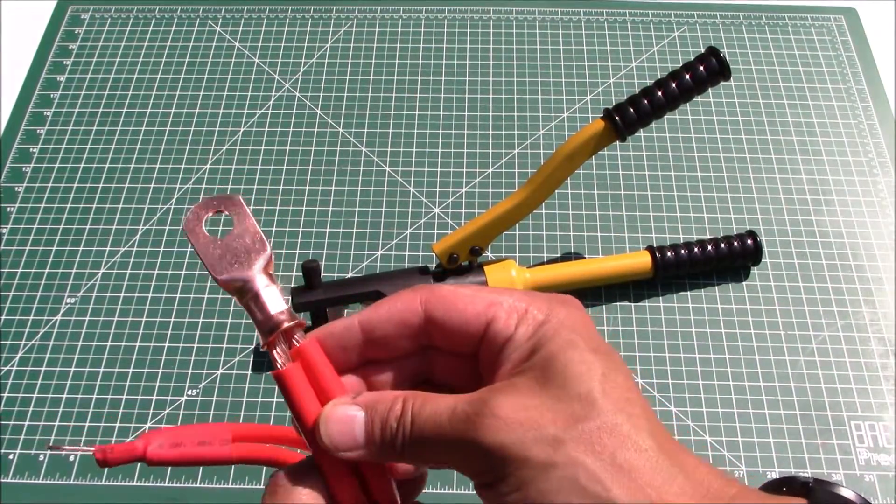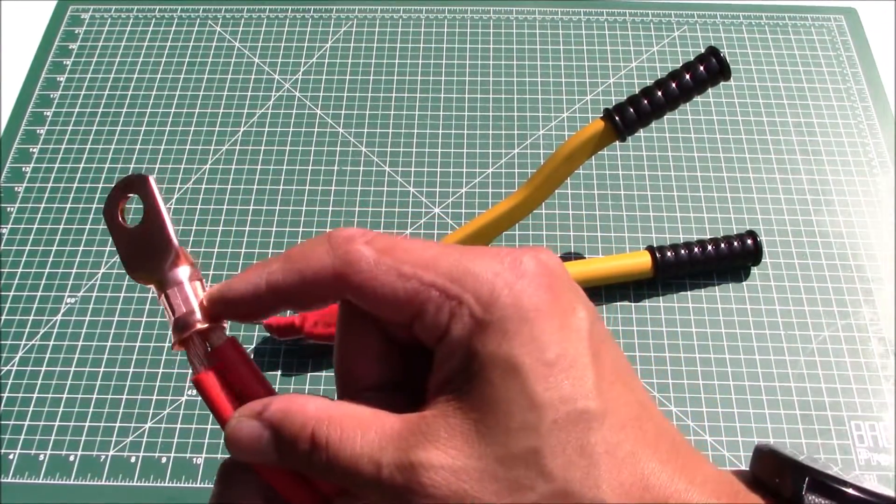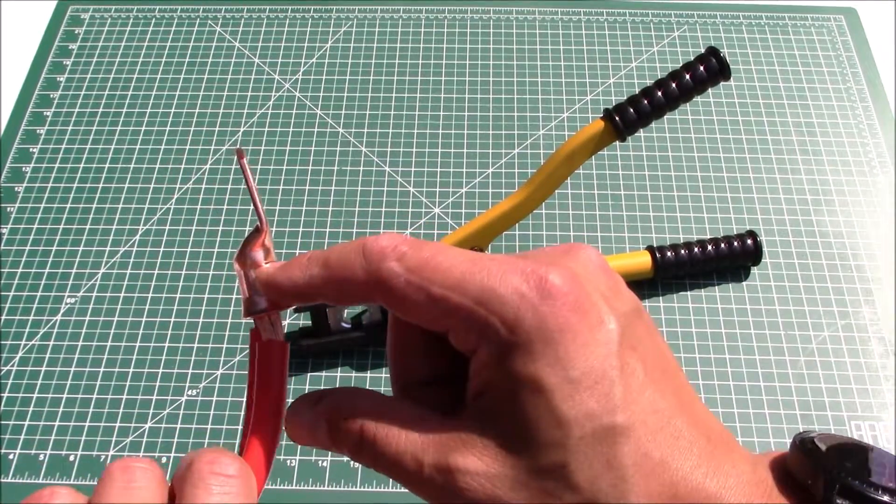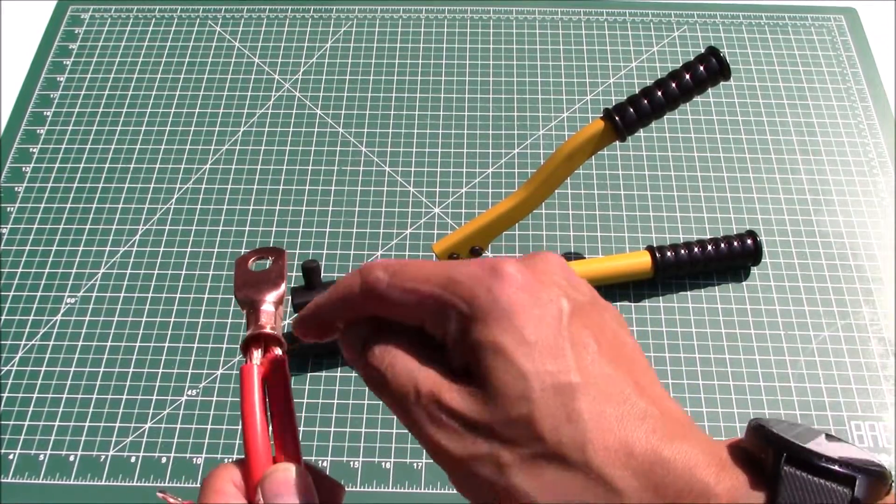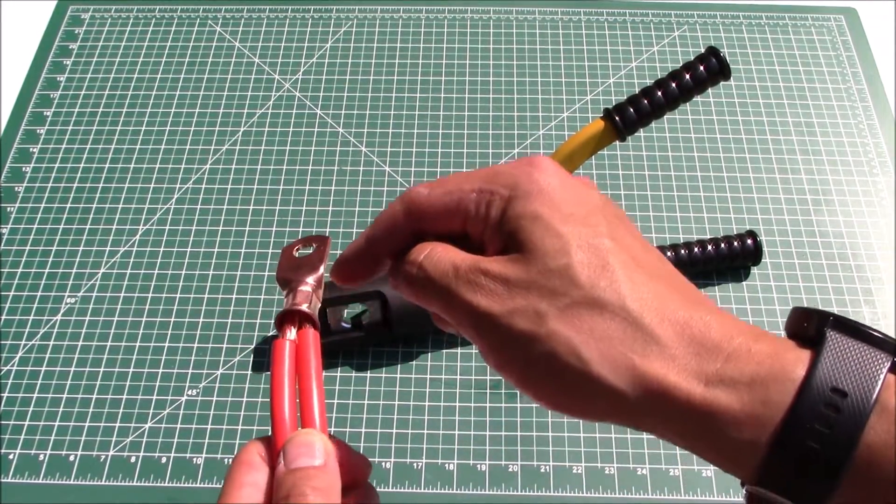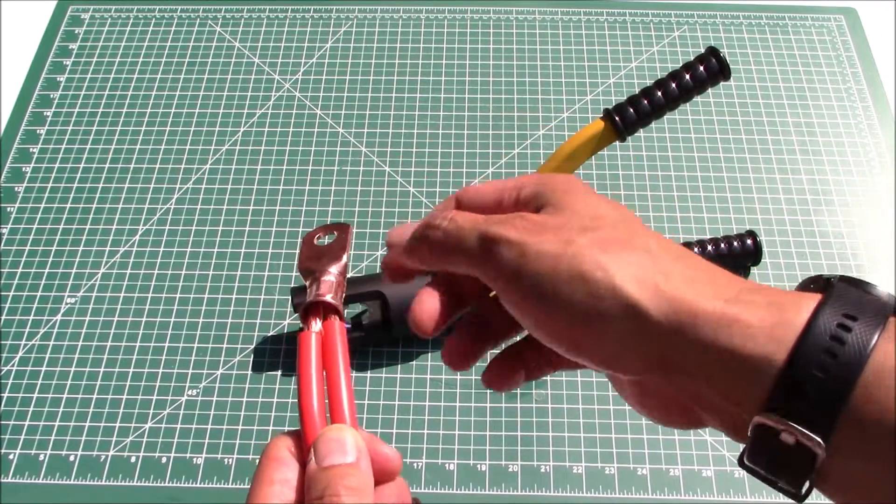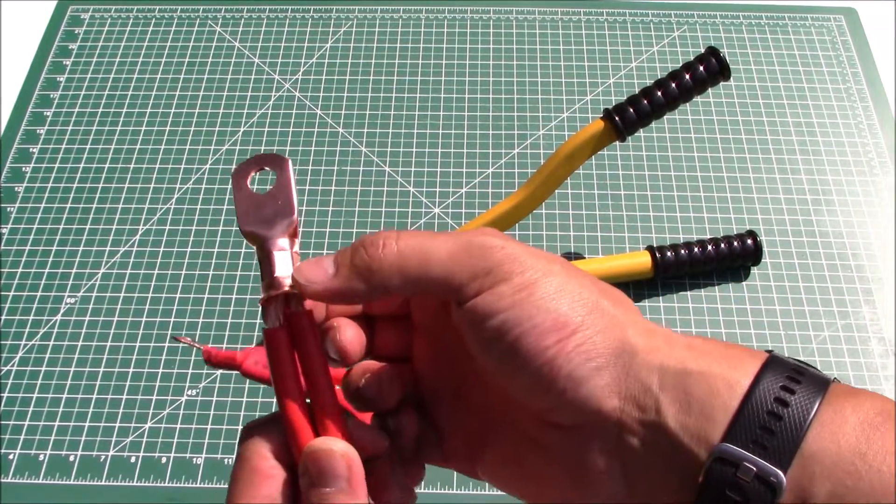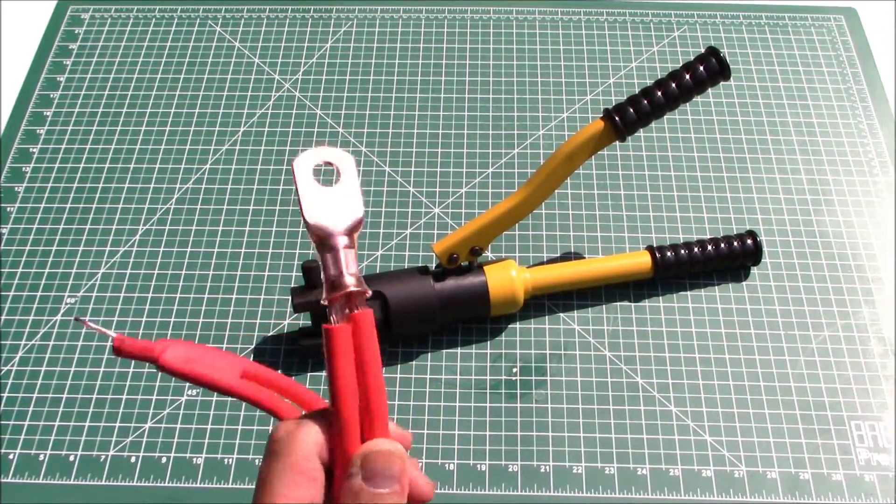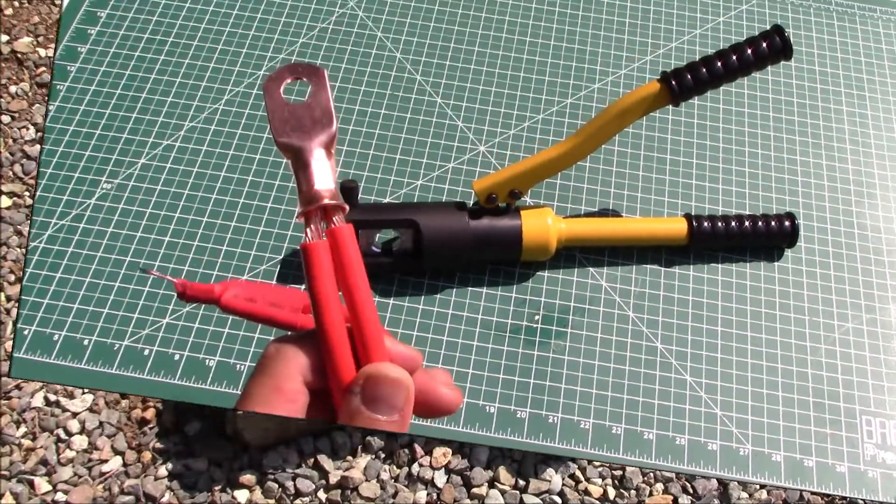We finished with the first crimp and as you can see what it's done is basically smashed the lug down around the wires. Now again because these wires are not exactly - they're a little bit too small, this lug is too big for it - it's actually not very tight right now. So I'm actually going to crimp it again one more time down here to make it hold a little bit better.